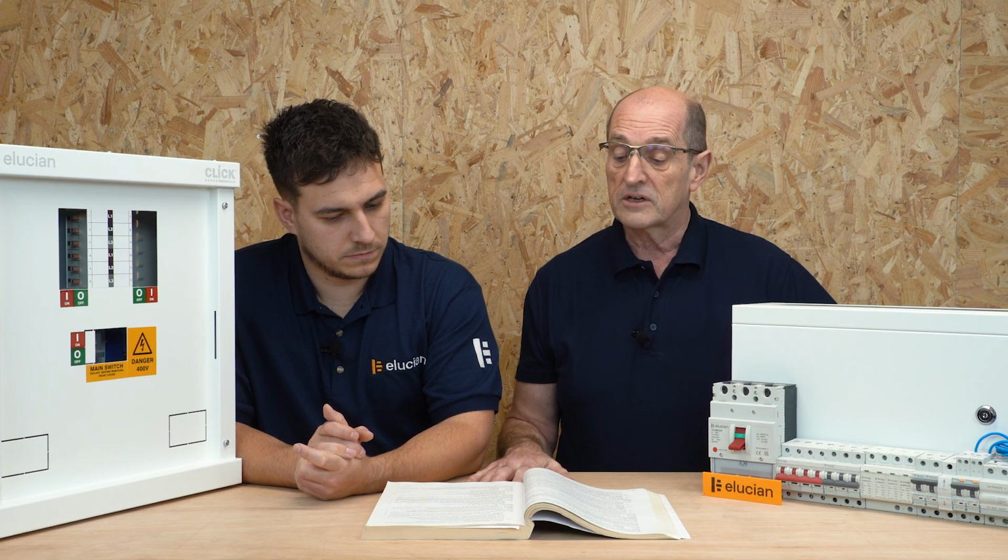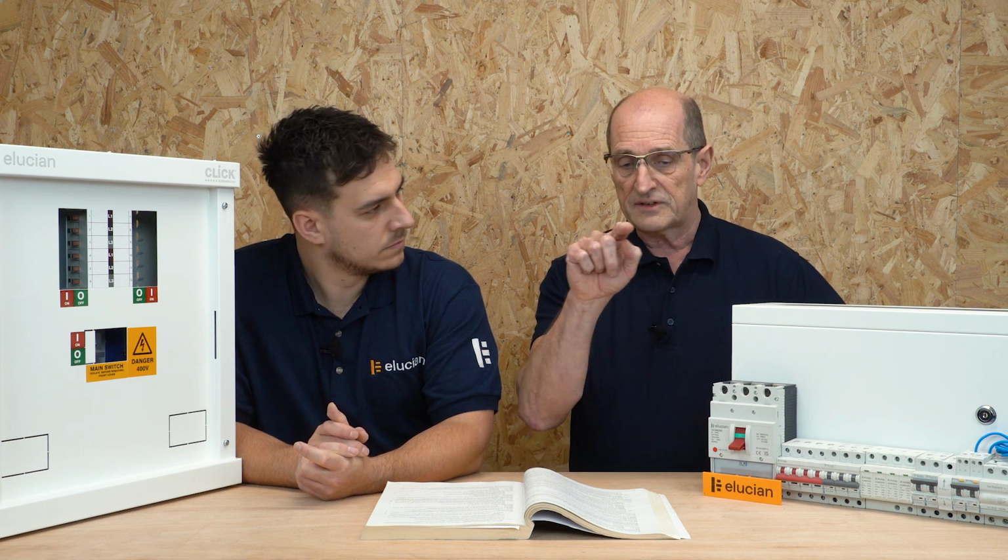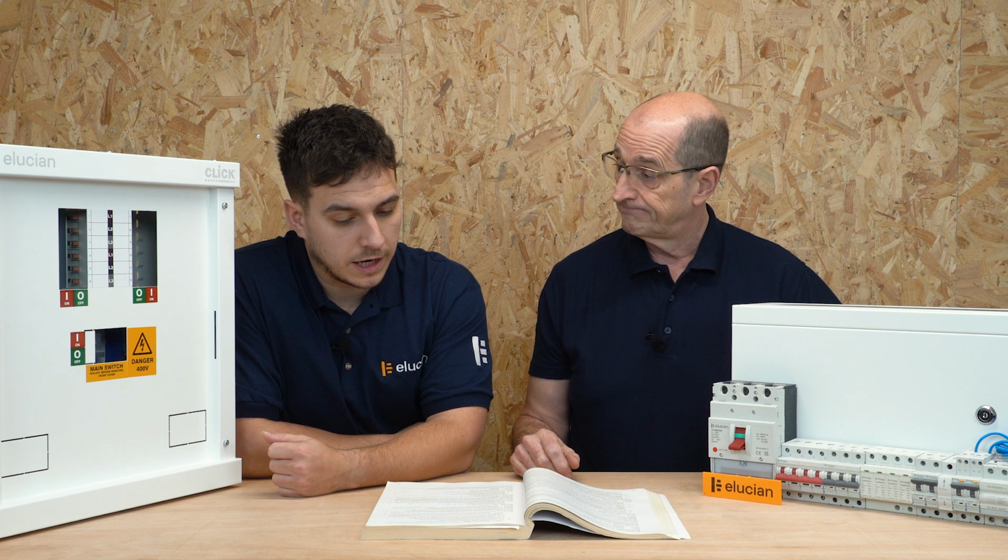The next bit in the list is for residual alternating currents superimposed on a smooth DC. Again, we're into slightly more complex areas, but it's all a function of the load. You've got residual pulsating direct current superimposed onto smooth direct current. You've got residual pulsating rectified direct current, which results from 2 or more phases. So again, this is a DC that always sits above the line, but it's going up and down. So it's a case of how do I not get tricked by this tweaking DC that has all the appearance of an odd AC. And then finally, for residual smooth direct currents, whether suddenly applied or slowly increased, independent of polarity. It sits under all of that, and a Type B gives you a functioning device even when all that stuff is happening. Quite clearly a clever piece of equipment then.